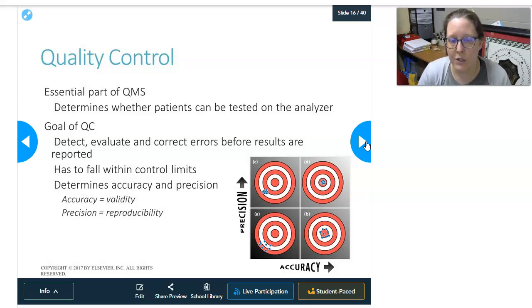And that determines accuracy and precision of the analyzer. Accuracy has to do with validity, or how close to the true value it is. If we look at these targets, the true value is the center. If your analyzer is hitting center every time, it is accurate. So these two are both representations of high accuracy. These are representations of low accuracy because they're off center. They're hitting below here and off to the side on the target, and these are hitting in the middle. So these two are accurate because they're hitting the target value. That means, for example, if your patient's actual glucose in their specimen is 88 and you're testing it on your machine, you actually are getting 88.